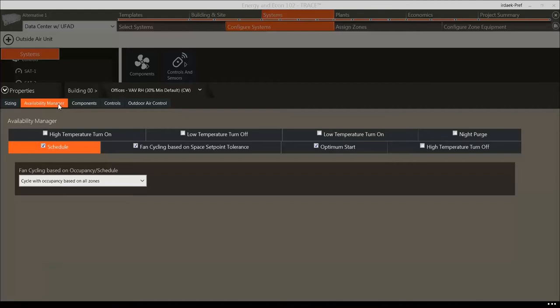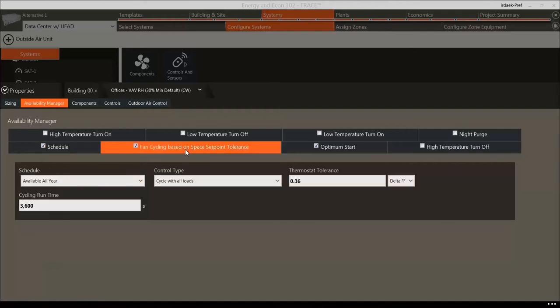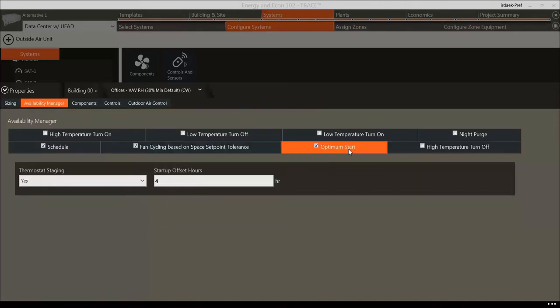The Availability Manager section controls many of the schedules for when the system is allowed to run. Users can control the overall fan schedule based on occupancy or schedule from the Schedule tab, or based on Thermostat Tolerance from the Fan Cycling Based on Space Setpoint Tolerance tab. Optimum Start allows users to configure the Optimum Start schedule, which allows the heating and cooling equipment to start operating before the building becomes occupied so that the building has been brought to the set point temperature for occupant comfort.